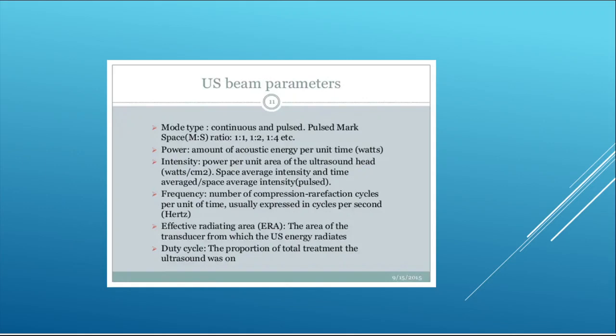Frequency is the number of compression-rarefaction cycles per unit of time. The intensity is always in watt per centimeter square, and the frequency is in hertz. Effective radiation area, ERA, is the area of the transducer from which the ultrasound energy radiates. The transducer is the head by which the radiation is transmitted. Duty cycle is the proportion of the total treatment time the ultrasound was on.